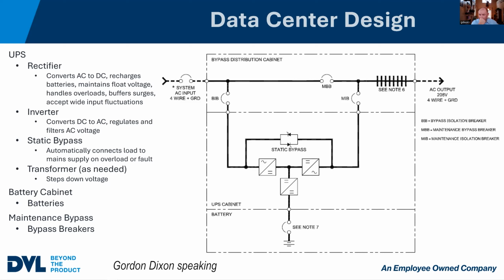To prevent a dual feed, to prevent a dual input into the DC load, into the batteries. So it's protecting the batteries. Batteries are expensive. They cost a lot of money to replace, so you do want to protect them. The static bypass helps that, but it also helps bypass internally, right? If we're not using it, right? So the UPS isn't even engaged.